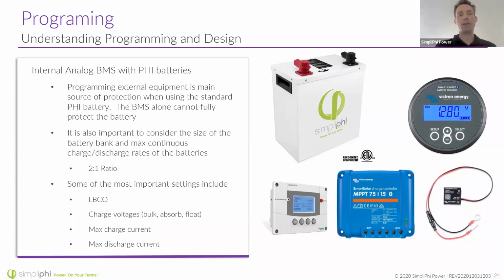So that means for our batteries, there's a 2-to-1 ratio. What do we mean by a 2-to-1 ratio? Our batteries are all rated at a C/2 discharge rate. What that means is the battery can discharge its entire capacity in 2 hours. C/2, the capacity per 2 hours, right? A C/1 discharge rate would mean the battery can discharge it in a single hour without damage. A C/20 discharge rate, which is typically the discharge rate used for lead acid testing, would mean that the lead acid battery would discharge over 20 hours.